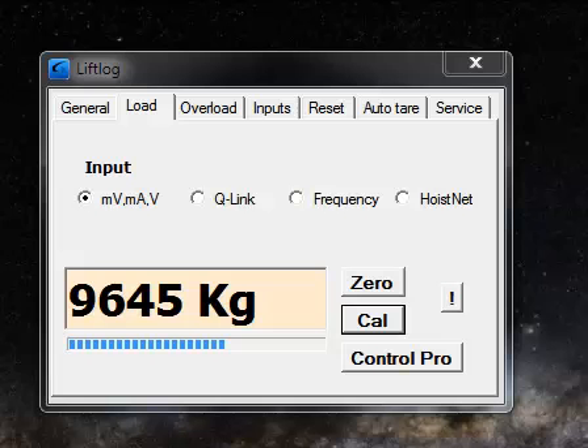Hi, in this video I want to demonstrate a little trick that you can use to fine-tune the calibration and the zero of a Liftlog, or indeed of any of our load sensing products. Sometimes when you do a calibration, it ends up just being a little bit off. In this case we calibrated for 10 tons and it's showing 9.645 tons.